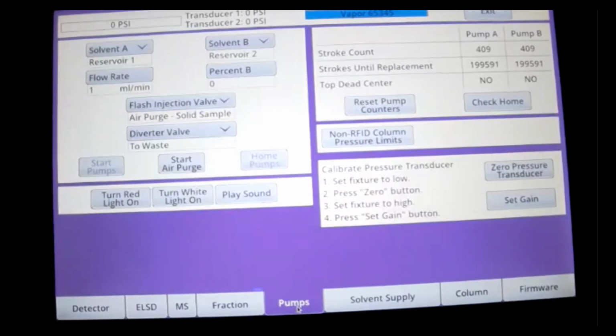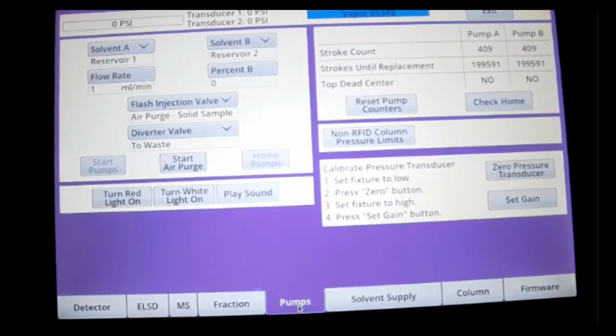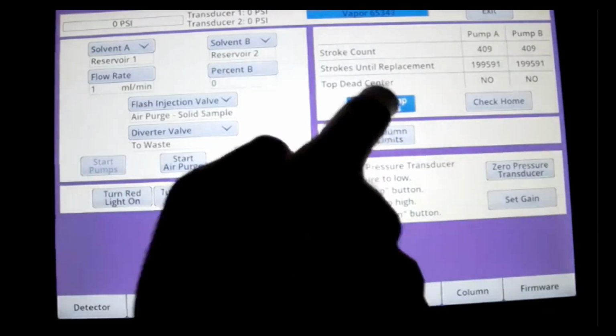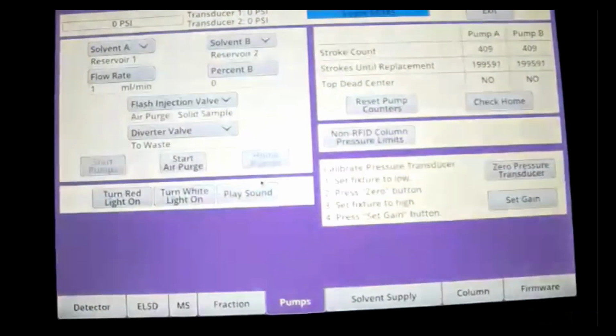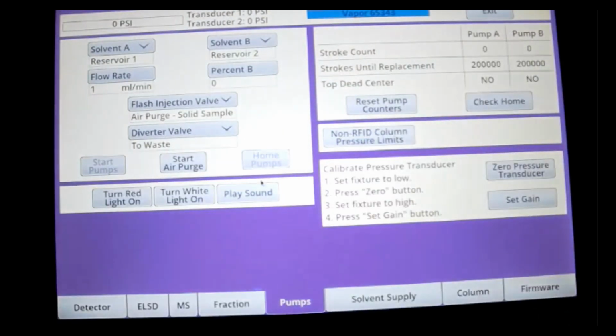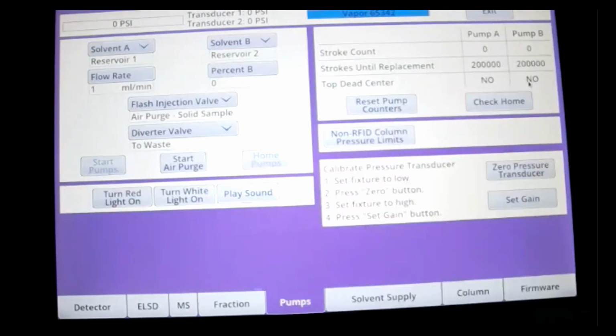Pumps, here's where you reset your pump stroke count. Holy cow, I'm only at 400 strokes each, but I just replaced my seals and I'm going to reset my pump stroke counter. So that went from 400 strokes each to 0. And as you can see, the strokes until replacement is 200,000. We talked about this earlier. So when it approaches, say, 150,000, it's going to start throwing up warnings. And if you exceed 200,000, it's going to tell you to contact us.